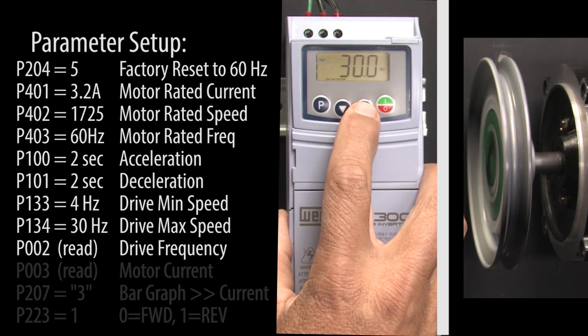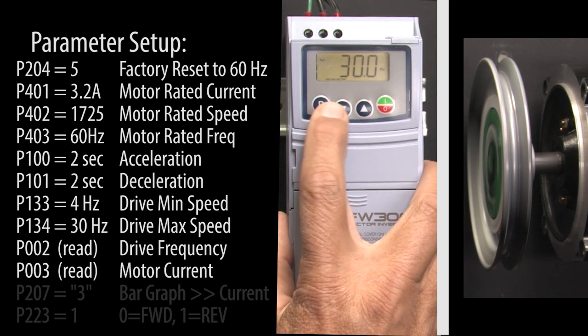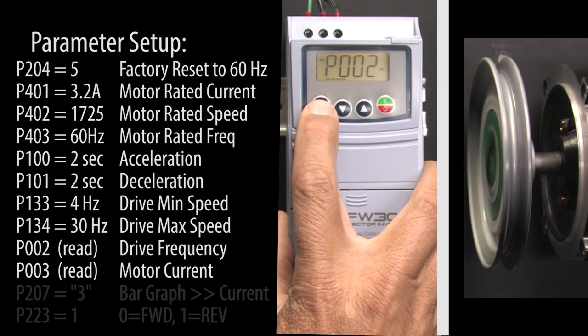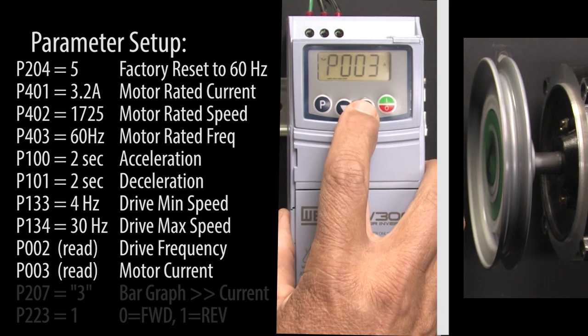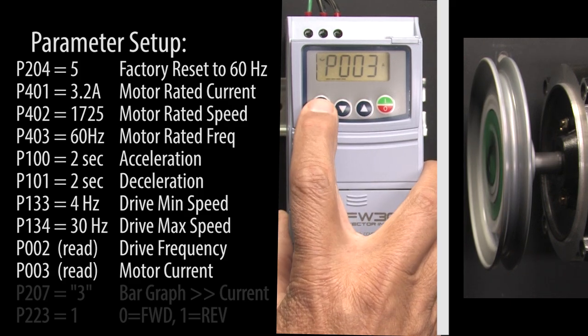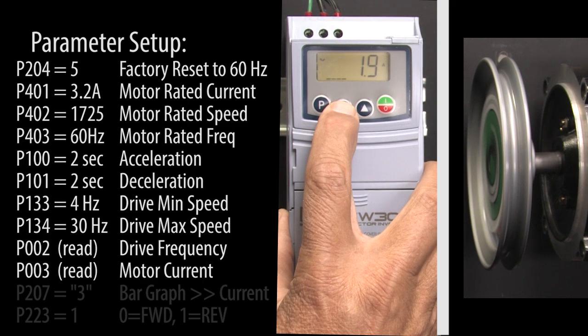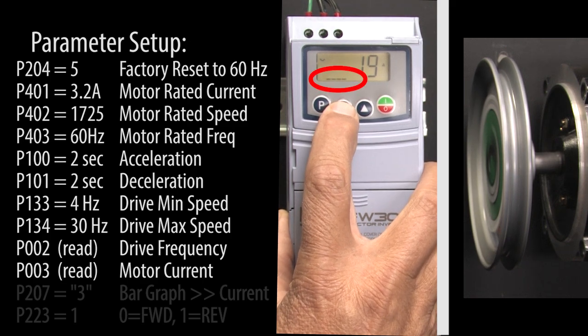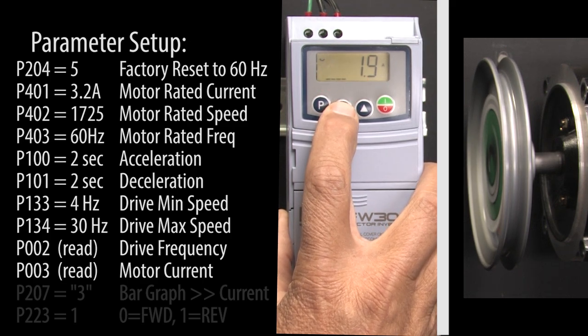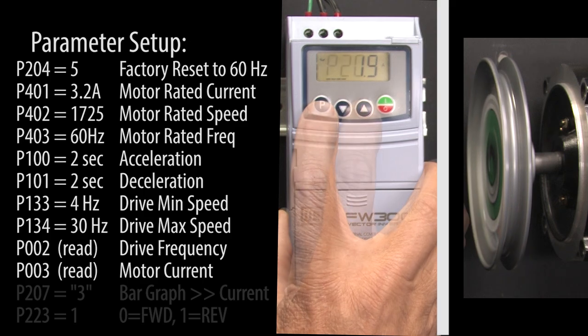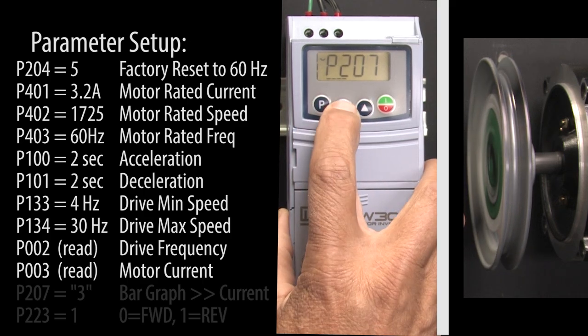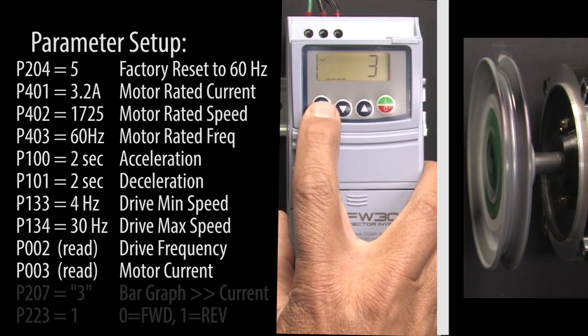To view the motor's current, press P to exit the frequency parameter. Go to parameter 3, which is the motor's current, and press P to see the value. This bar graph down here is also showing the motor current because the bar graph parameter — which is parameter 207 — says display parameter 3, the motor's current.